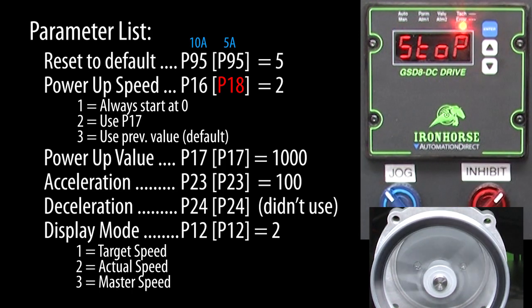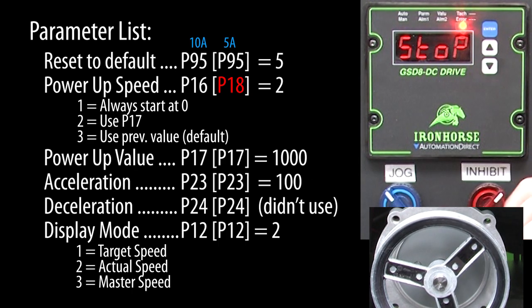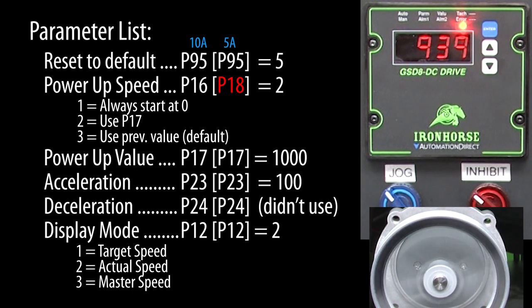This time let's scroll to parameter 0 and hit enter to get out of parameter entry mode. Now if I inhibit the motor and wait for it to stop, then remove the inhibit, sure enough our display is now showing us the actual speed of the motor.